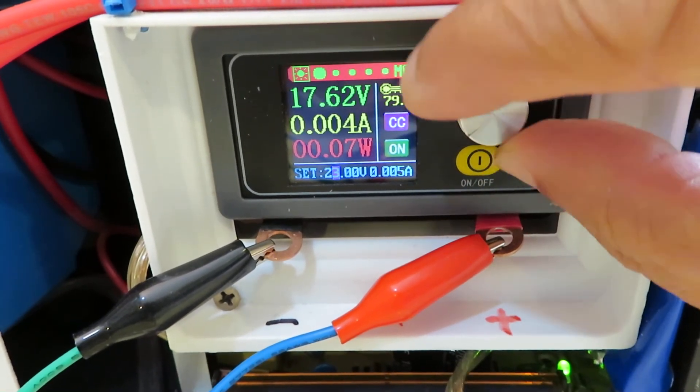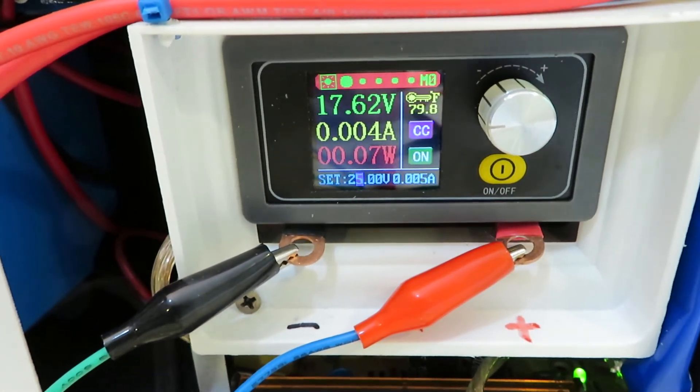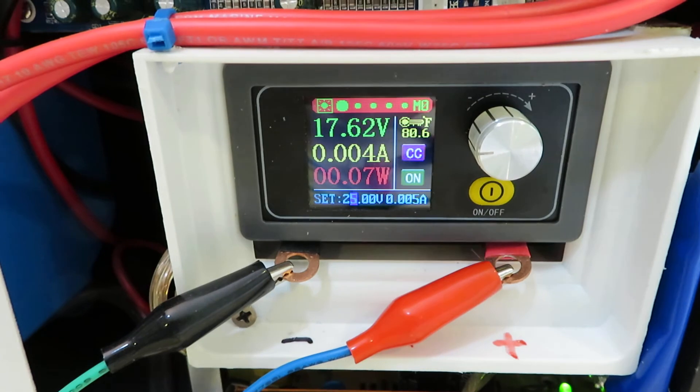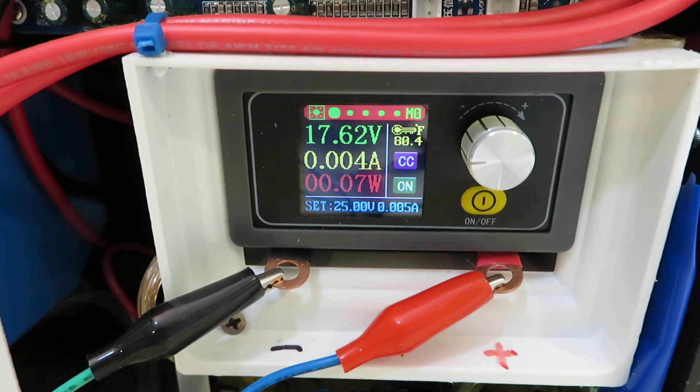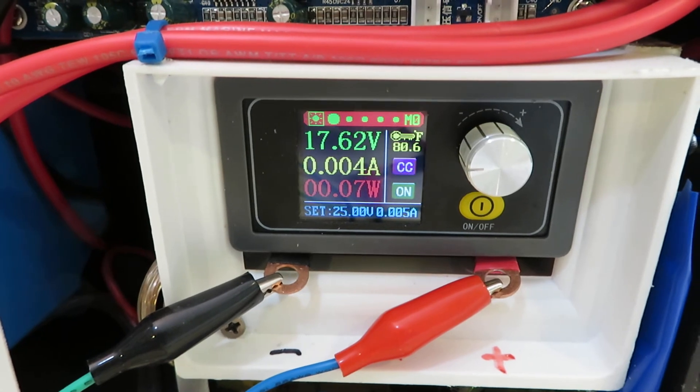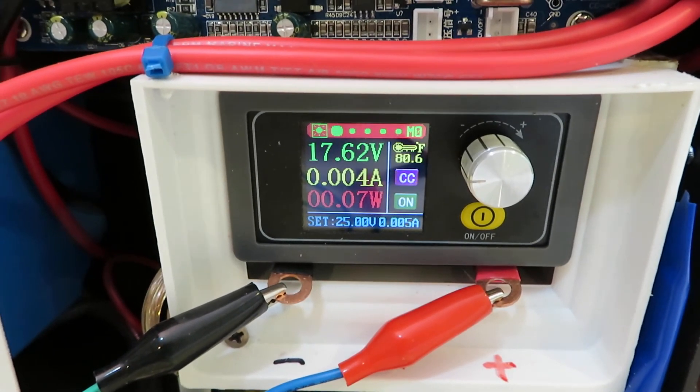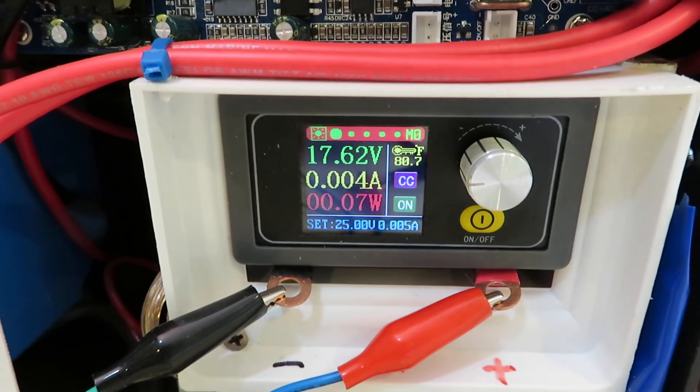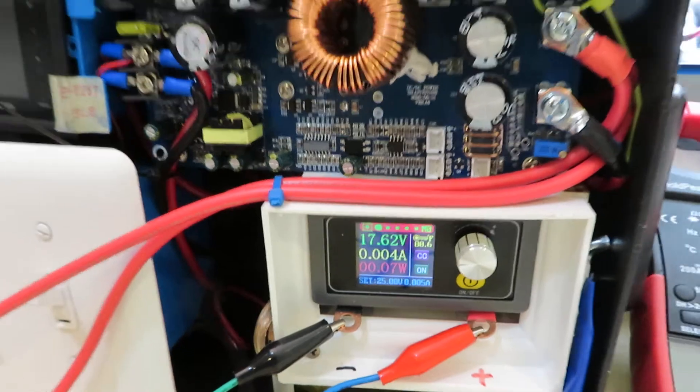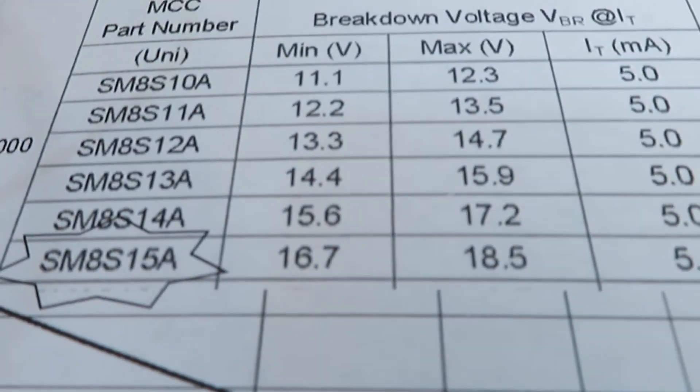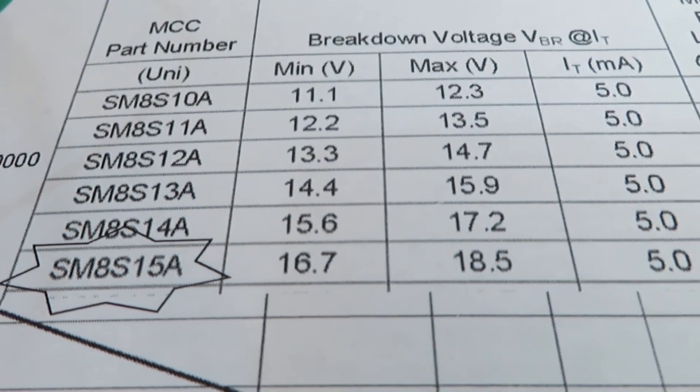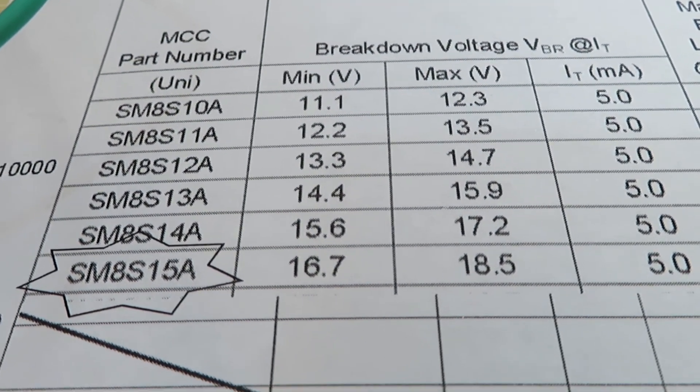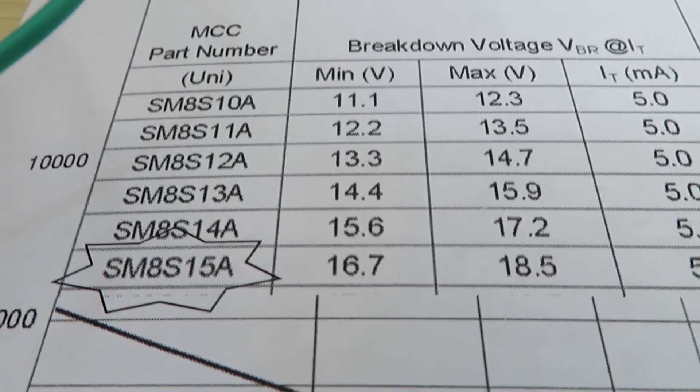Let's go to 25 volts. Okay, it's still clamped at 17.62 volts and about 4 milliamps. So 17.62 volts is within the spec. The spec is 16.7 volts minimum and 18.5 volts maximum.